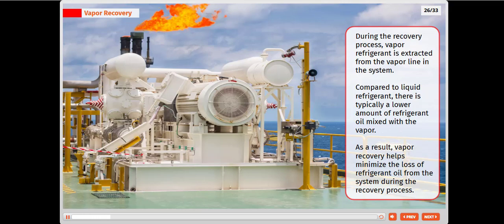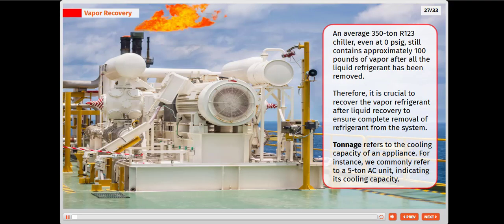During the recovery process, vapor refrigerant is extracted from the vapor line in the system. Compared to liquid refrigerant, there is typically a lower amount of refrigerant oil mixed with the vapor. As a result, vapor recovery helps minimize the loss of refrigerant oil from the system during the recovery process. An average 350-ton R123 chiller, even at 0 psig, still contains approximately 100 pounds of vapor after all the liquid refrigerant has been removed. Therefore, it is crucial to recover the vapor refrigerant after liquid recovery to ensure complete removal of refrigerant from the system.